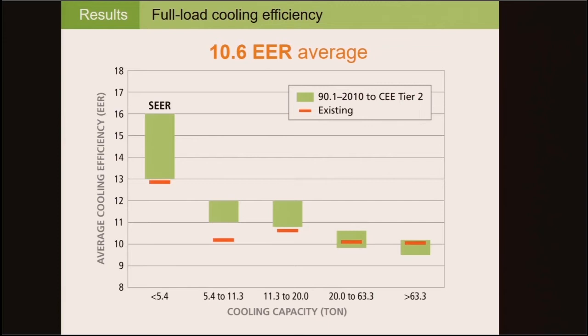In RTUs with cooling capacities below 20 tons, the average existing efficiency is below the code minimum and well below the Tier 2 recommendation, suggesting considerable opportunity for improved efficiency in smaller RTUs. For larger RTUs with cooling capacities between 20 and 63.3 tons, the average existing efficiency is between the code minimum requirement and the Tier 2 recommendation. Since their efficiency is already relatively high, there is a limited opportunity for increasing efficiency. For the largest capacity RTUs with cooling capacities above 63.3 tons, the average existing efficiency is near the Tier 2 recommendation, leaving little opportunity for increased efficiency.